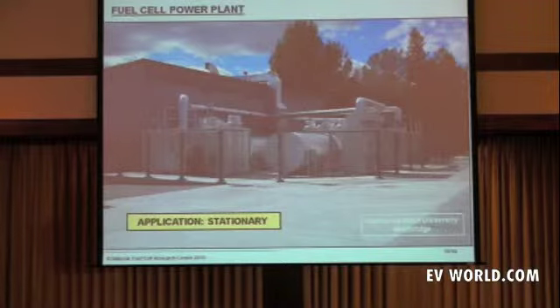Students can walk through and see some of the interesting ways we can further reduce our carbon signature over the high efficiency that this system already provides. This system provides fuel-to-electrical conversion efficiency of 50%, and the waste heat recovery gives it an overall efficiency exceeding 80%.